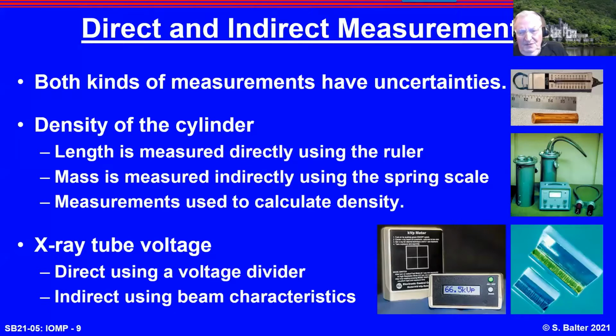If I look at X-ray tube voltage, it is possible to use a direct voltage divider across the X-ray tube terminals. And here you see an example of one of these from the 1960s. It's possible to measure these indirectly by measuring the characteristics of the X-ray beam. This can be done either analog or digital. On the extreme lower right, you see an analog voltmeter. This works from the physical principles of comparing attenuation in the Compton range against photoelectric, matching the wedges. This derives from actually Roentgen's third paper, where a similar test for beam hardness is described.